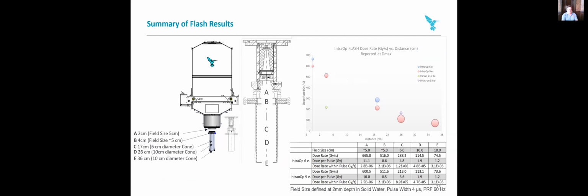So what we've done, in taking some standard measurements to talk to people about it, is come up with a series of distances. One at point A, then B, C, D, and E. A is right at the exit window, the beryllium window of the LINAC, where the electrons emerge. That point is just a few millimeters off of the window. It's not actually flush against the window, but we have a mechanical bracket there. You can locate animals there and test fixtures there. You can locate film there, and that's how we measured it. That's a 4.5 or 5 cm exit window. That's how large the beam comes out of our machine.